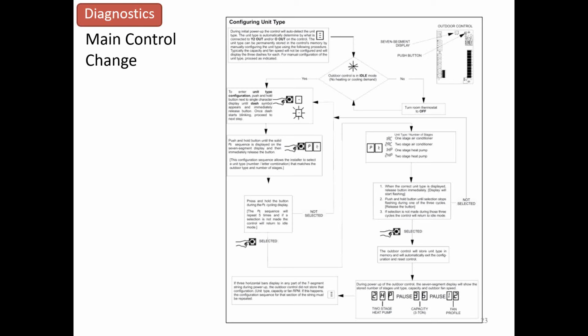So this is also a great diagnostic, to be able to push the button and see what's going on. But when you program it, the literature is a little crazy. When I looked at it the first couple times, I saw it myself, and reading through it, it's a little confusing. So if you push the button, it's going to come up and it's going to blink. And when it does, you push and hold it again. Then it starts running through different options. It'll say PT, PU, CU, different options that are in there. Once the option comes up that you need, push and hold again, and then release it, and it'll start running through a menu inside of that. And that's how we get it in the different menus.